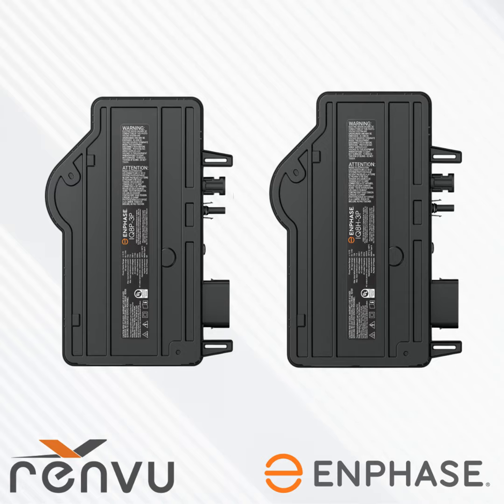Because Enphase is built on that distributed AC architecture, it's inherently rapid shutdown. If you look at the verbiage in 690.12, the proximity of the inverter to the panels matters, and for us that means we're just rapid shutdown compliant. You don't need an auxiliary rapid shutdown switch.